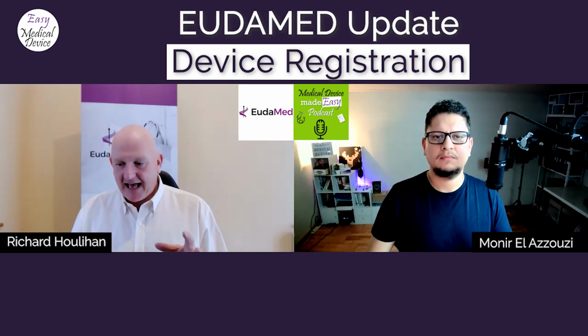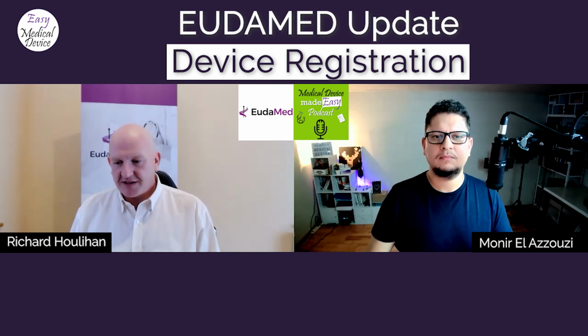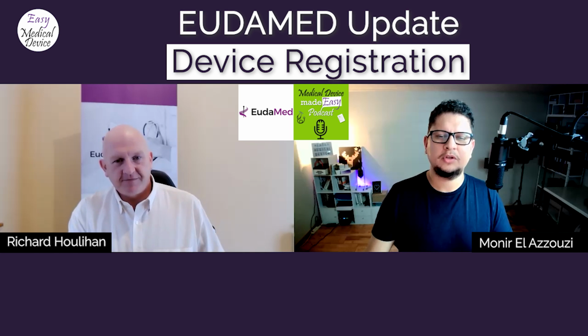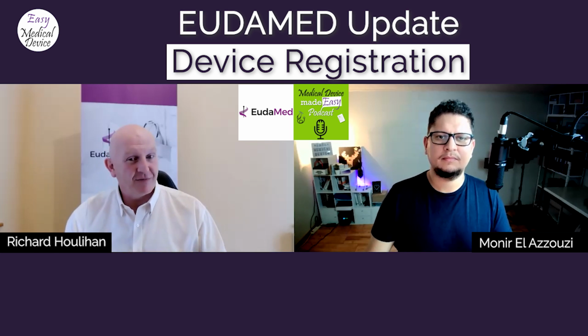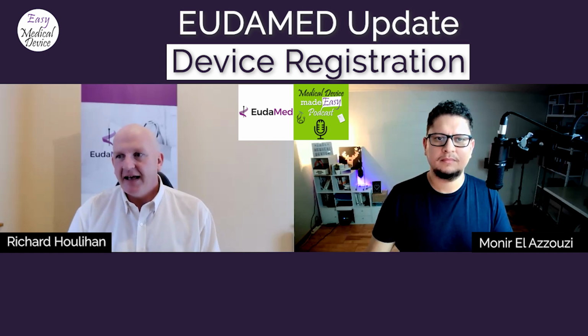But the biggest advice I give, obviously use our products, which is fantastic, but over and above that, make sure your data is correct before it goes anywhere near EUDAMED. Because when you're uploading the data, you're only allowed 300 entities, 300 UDI-DIs in one XML file. So if you've got 3,000, obviously it's 10 files. But if one individual field in the XML fails, the entire XML file is refused. So then you have to manage these all in batches, because you can't upload it twice. Then you have multiple versions, and it just gets really complicated and messy. So make sure your data is perfect before you go anywhere near EUDAMED.